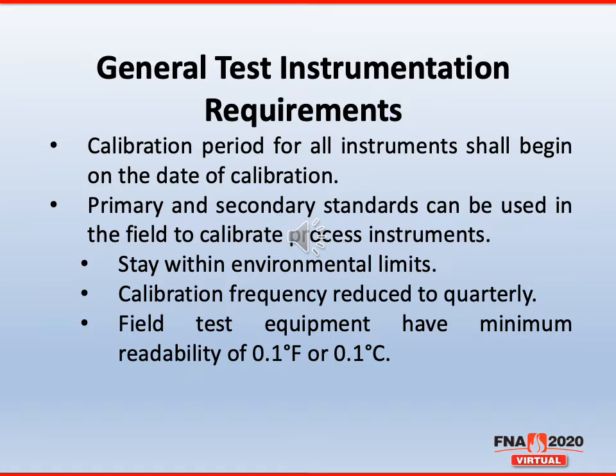The one thing we do hold back on is that the calibration frequency for those test instruments, if they are brought out onto the shop floor, would be reduced to a quarterly interval. For instance, a primary standard, if it stays within the laboratory, has a calibration interval of 3 years. A secondary standard's is once a year. But once those are removed from the laboratory environment and brought into the field, the calibration frequency drops to quarterly.